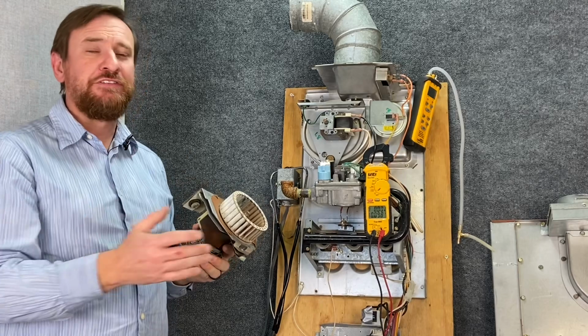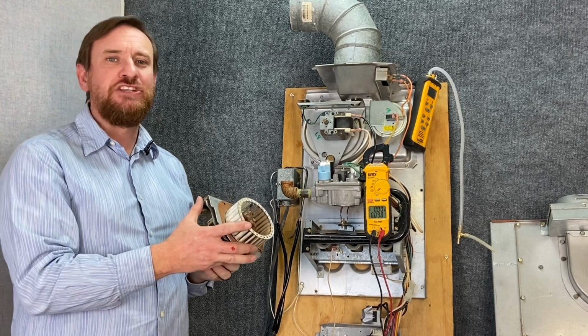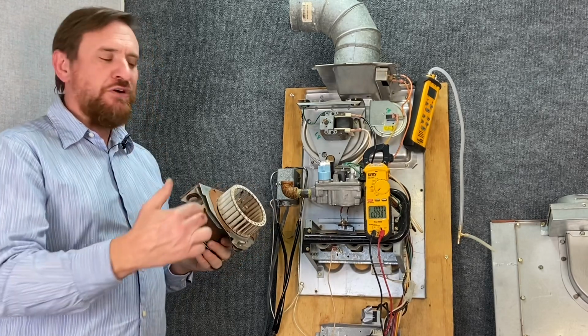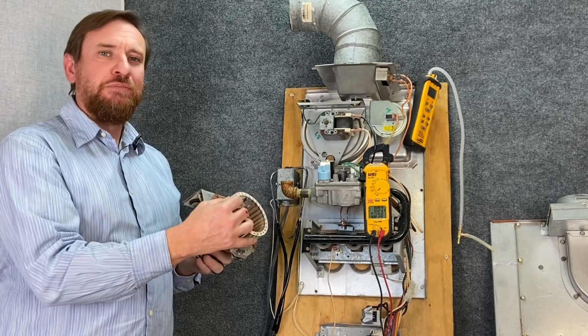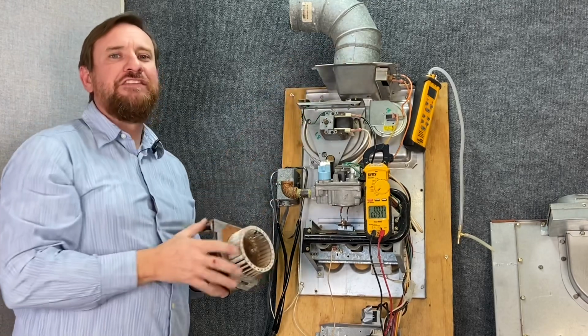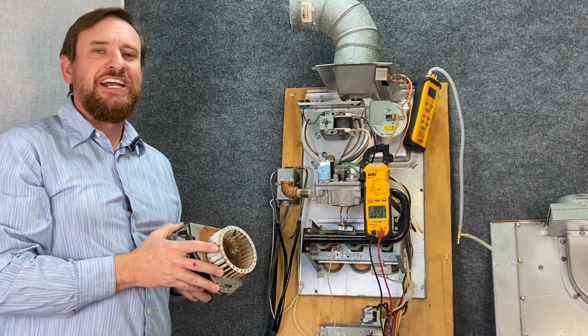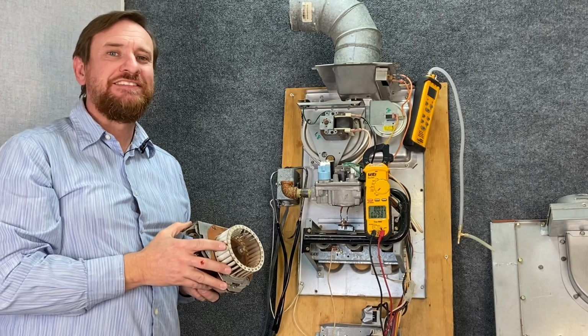A byproduct of combustion is water vapor, or H2O. That water vapor, H2O, will build up on this blower wheel. It'll build up in the flue pipe, and even worse, it builds up in the heat exchanger and actually eats the heat exchanger away from the inside out.